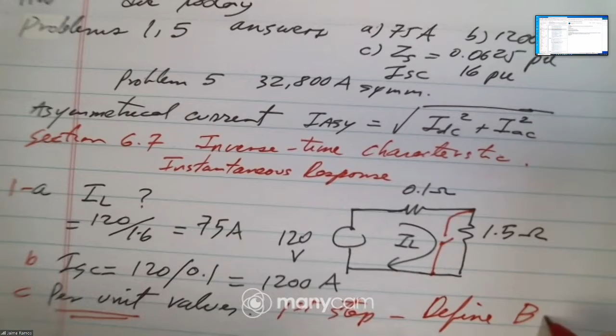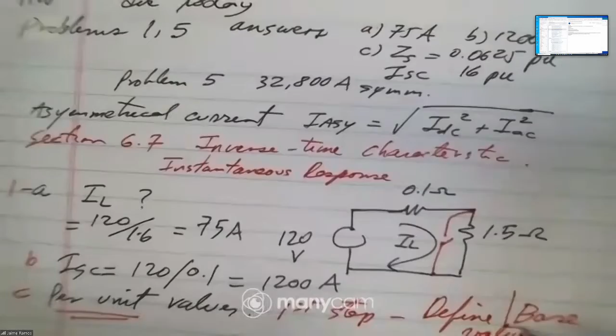Then C, it says per unit values. Okay, per unit values. So when we say per unit, the first step is to define base values. Base values, okay? So in this case, we need V base, so naturally pick up 120. And then we have several choices. We can, for example, make I base equal to I load, which is 75 amps. 75, sorry.